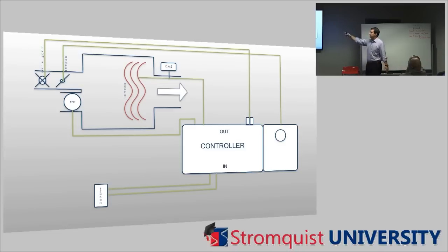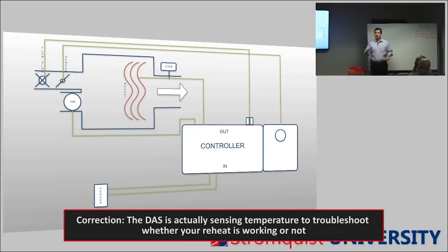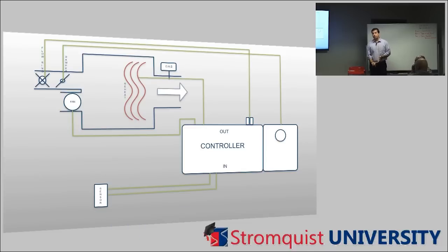If you see that your fan's on and your damper's wide open, maybe your reheat strip's on because you're wanting heat, but still something's not quite right. Well, you look at your discharge air sensor and it says zero. Well, you know something's not working. Fan's not working, or the air handler down line's not working. So you can diagnose a lot of stuff right from your desk. These days, right from your iPad or tablet or smartphone. You can stand right underneath it and start pulling up things and trying different things before you ever grab the ladder, which goes back to productivity savings, right?